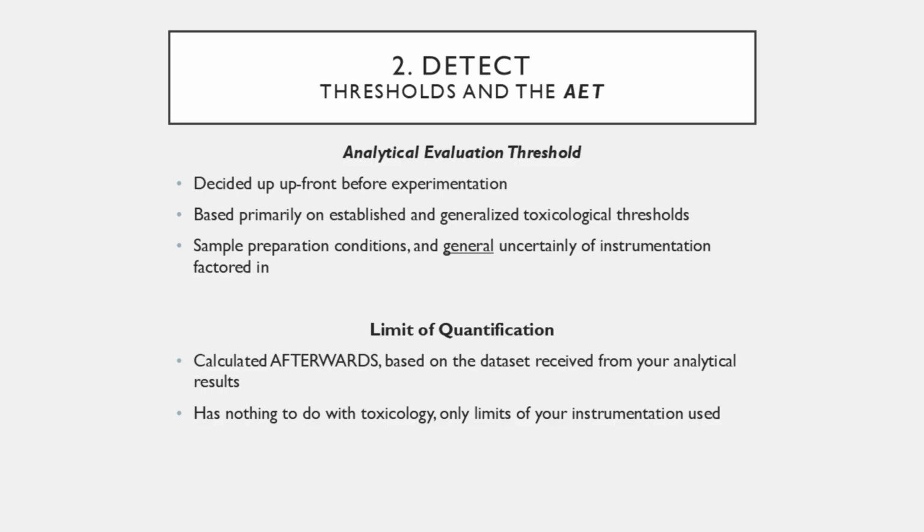So, the AET is what the FDA is concerned with you being able to detect. Because if you can't detect anything below that, then how can you even say that something risky isn't there? You're not going to be able to detect it, and it's not because it's not there. It could be, for all the FDA cares, and they're going to take the worst case assumption. They're going to assume it's there unless you can prove otherwise. The limit of detection is simply what you're able to detect in the first place.